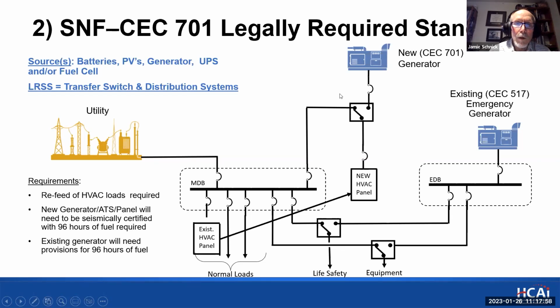In this case, this whole new system, the panel, the transfer switch, the generator would all need to be seismically compliant. The provision for the generator of 96 hours of fuel would be required. And the existing generator, which backs up the essential and the life safety and the equipment branch, would need to have provisions made to have 96 hours of fuel. Obviously, with the new generator introduced, the intent is to keep the building occupied and within temperature range as specified. And we would need to keep the building's emergency system up and operational for the entire 96 hours as well.